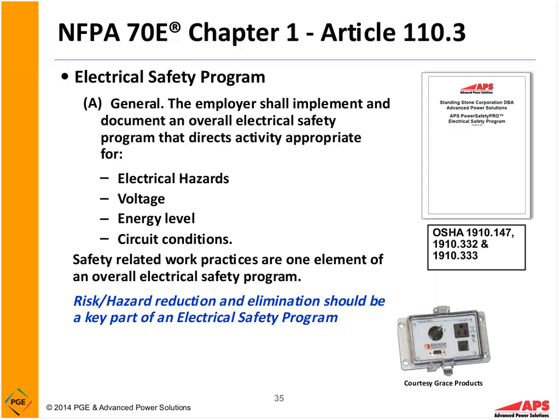So an electrical safety program: 70E calls for the employer to implement and document an overall electrical safety program that directs activity appropriate for the electrical hazards that are present, the voltages, the energy levels, and the circuit conditions. Safety-related work practices are one element of an overall safety program. In a nutshell, our safety program should be designed so that a lot of what we're doing is trying to design out exposure to the hazards. Not just putting on personal protective equipment and saying, okay, I've got the PPE on, I'm okay to work on this energized, but actually trying to figure out a way that I don't even have to be exposed to the hazards. I've given you an example here in the lower right-hand corner.